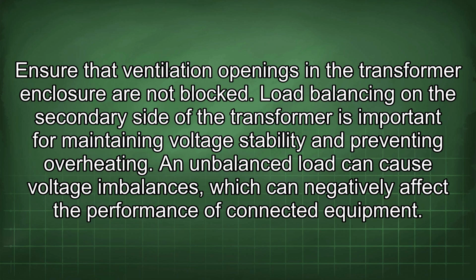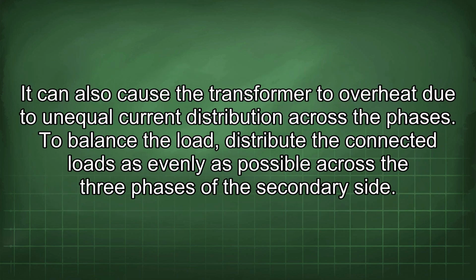Load balancing on the secondary side of the transformer is important for maintaining voltage stability and preventing overheating. An unbalanced load can cause voltage imbalances, which can negatively affect the performance of connected equipment. It can also cause the transformer to overheat due to unequal current distribution across the phases. To balance the load, distribute the connected loads as evenly as possible across the three phases of the secondary side.